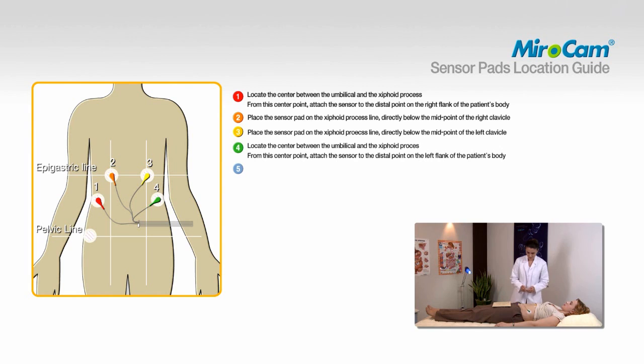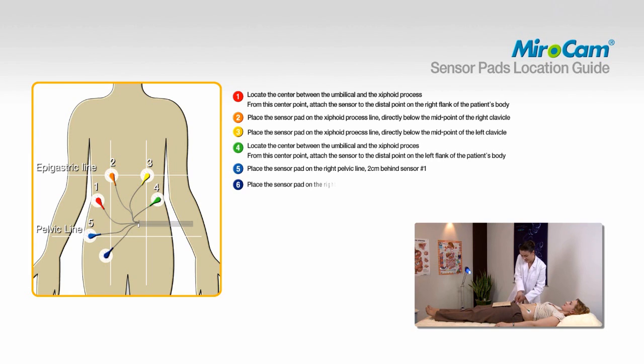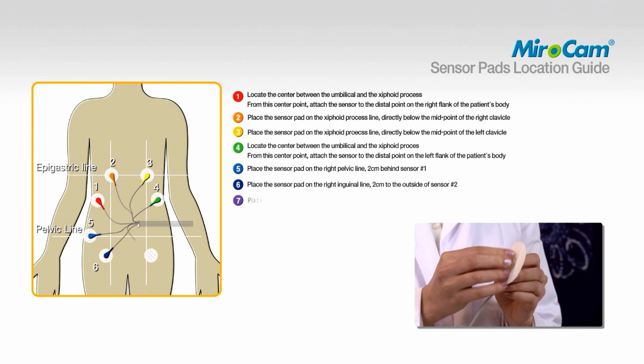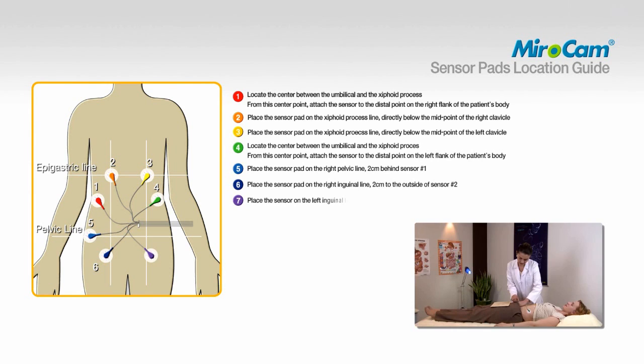To attach pad number 5, place the sensor pad on the right pelvic line, 2 centimeters behind sensor number 1. To attach pad number 6, place the sensor on the right inguinal line, 2 centimeters to the outside of sensor number 2. To attach pad number 7, place the sensor on the left inguinal line, 2 centimeters to the outside of sensor number 3.